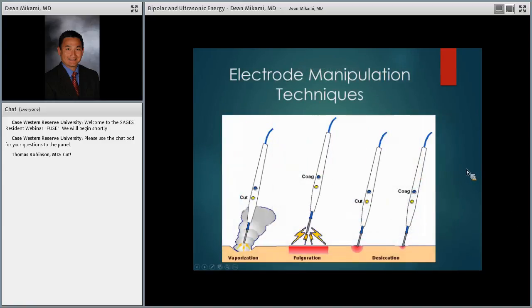Okay, so we talked about this a lot. This is very, very important. And for those of you that are going to take the FUSE exam in the future, you need to memorize the slide. When you vaporize something, you're holding your pencil above the tissue, and you're vaporizing it when you use cut. And remember, when you activate the active electrode in cut mode above the surface you're working on, you get sparks that fly off the end of the active electrode. It finds the surface area, right? Remember I told you it's trying to complete the circuit. The current is trying to get from the active electrode to the dispersive electrode. So these sparks fly off the end of your pencil, vaporizing the tissue beneath it. And then when you use coag mode, the same thing happens. It's the same power setting, but you have a higher voltage, and you get a much higher voltage activating on the tissue.